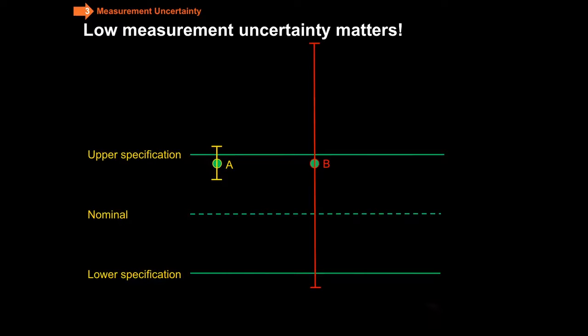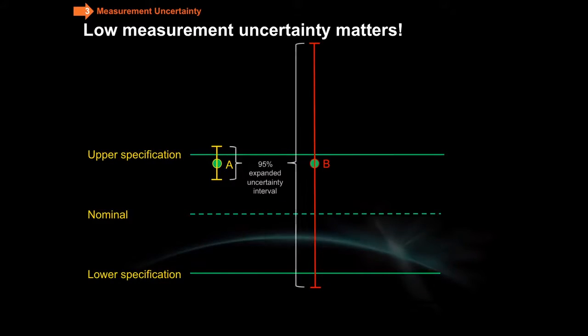Now you might have noticed on the slides that were slipping by before that we had highlighted in yellow that measurement uncertainty is essentially a statistical standard deviation. And that's important because those of you that know statistics know that if for reasonable distributions for which most instruments fall, if you take two of those, and in the metrology parlance they say k equals 2, you get the 95% expanded uncertainty interval.